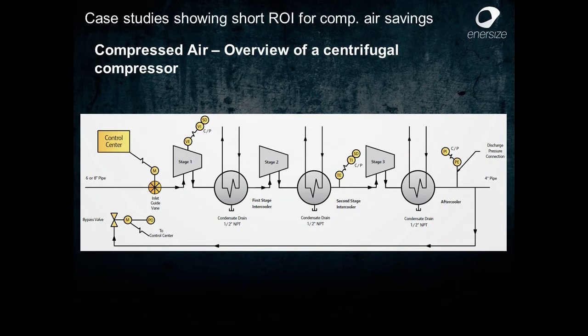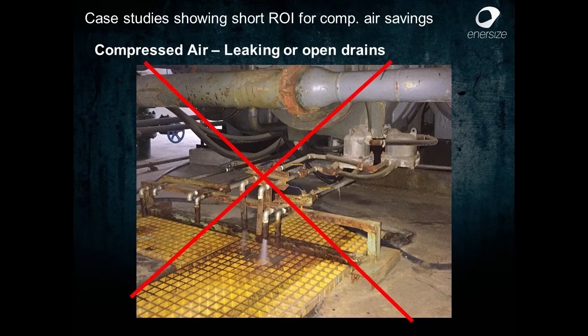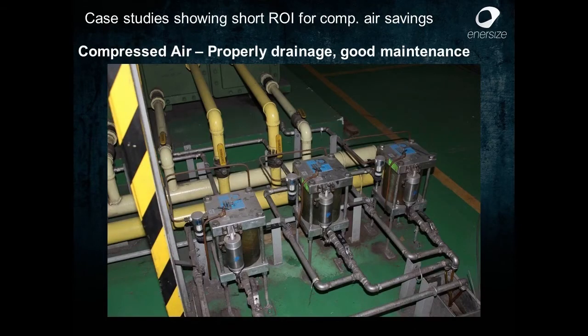I will show a few pictures of these condensate drains, also another compressed air classic where you can save some energy. What I see very often is completely open drains where they drain out the water from the intercoolers and aftercoolers, but not only the water, also a lot of compressed air. It is not the way to do it. You should, of course, do it like this, where we have the so-called zero loss drains. On top of that, in this system we collected the water and pumped it to a cooling tower later on. It will save water resources and also treatment of water for cooling purposes.